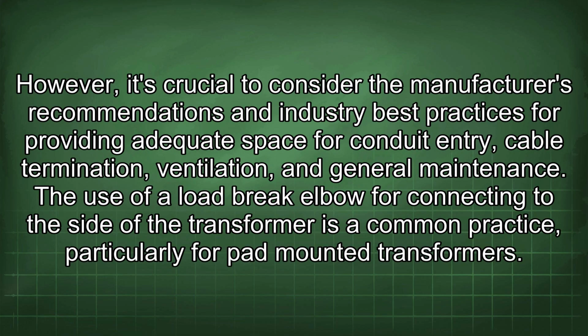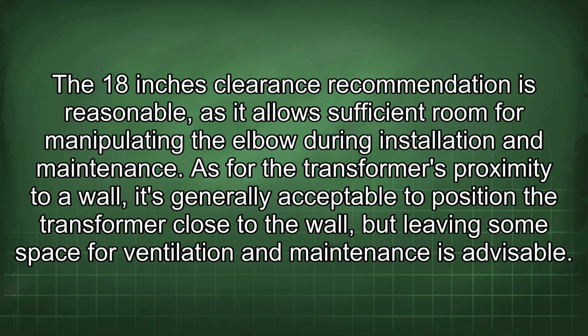However, it's crucial to consider the manufacturer's recommendations and industry best practices for providing adequate space for conduit entry, cable termination, ventilation, and general maintenance. The use of a load break elbow for connecting to the side of the transformer is a common practice, particularly for pad-mounted transformers. The 18 inches clearance recommendation is reasonable, as it allows sufficient room for manipulating the elbow during installation and maintenance.